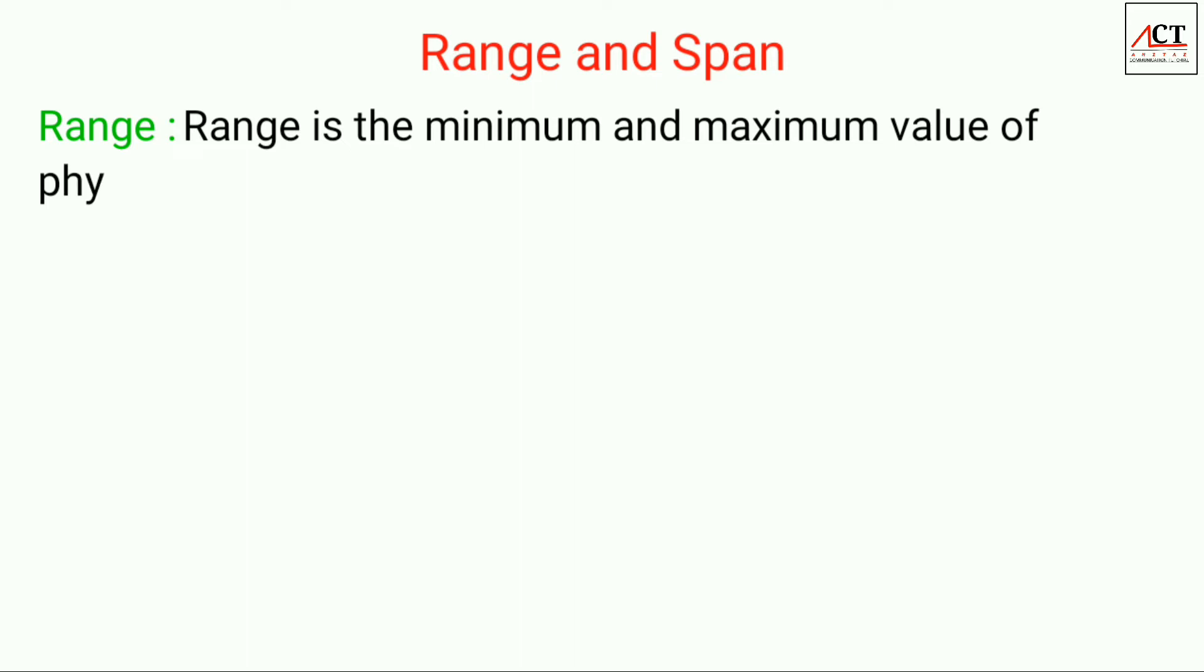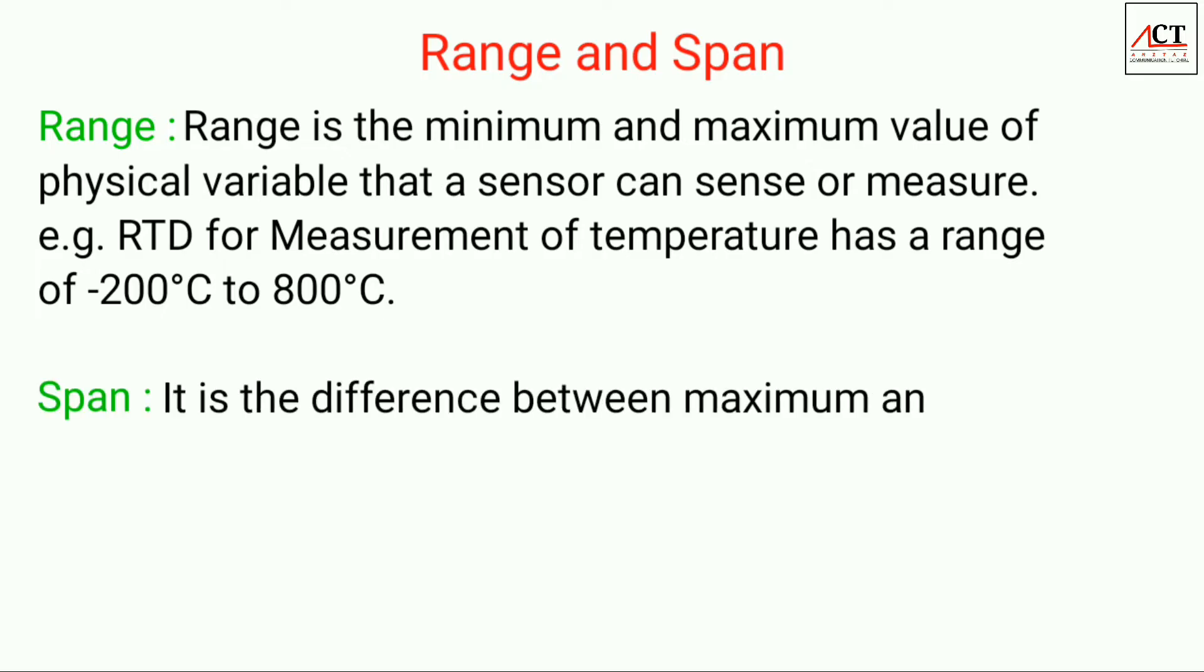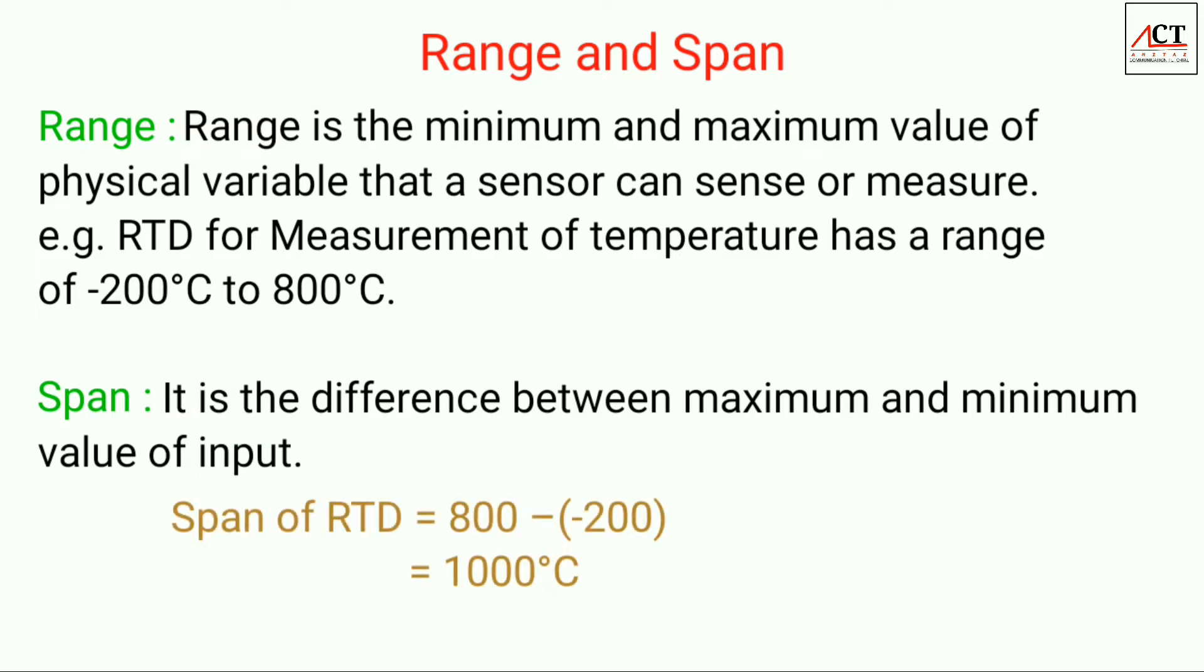Next static characteristic is range and span. Range is the minimum and maximum value of a physical variable that a sensor can sense or measure. For example, RTD for measurement of temperature has a range of minus 200 degree Celsius to 800 degree Celsius. Span is the difference between maximum and minimum value of input. So span of RTD in this case will be 800 minus minus 200 degree centigrade, that is 1000 degree centigrade.